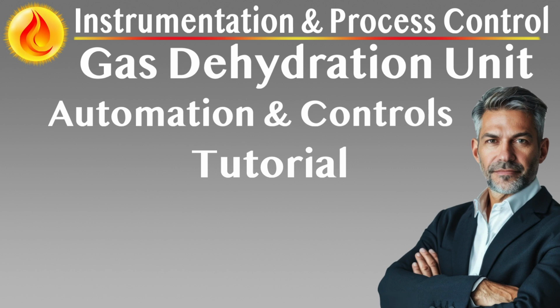Rich glycol level control. Guided wave radar, GWR, or displacer type level transmitters control discharge to the heat exchanger or directly to the reboiler. Low-level alarms prevent pump starvation. High alarms, LHH, prevent flooding. Hydrocarbon skimming, optional. Rich glycol is skimmed for condensate using interface-level controllers, with recovered condensate routed to waste oil or recovery system.